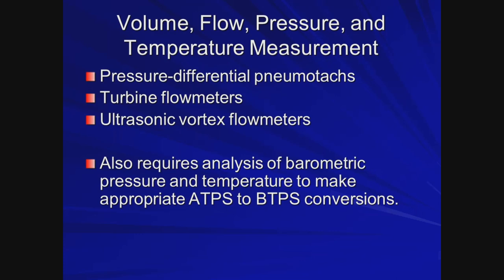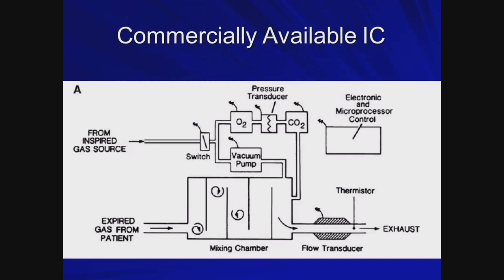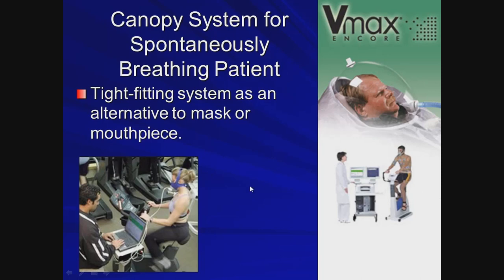There is a conversion from ATPS to BTPS involved. Internally, the system mixes the gas thoroughly, which is very important, then samples it and measures O2, CO2, and volume. Some systems use a hood or space-suit sealed around the patient for a tight seal; others use a mask system on a patient on a bike — it's just a matter of sampling the two gases.